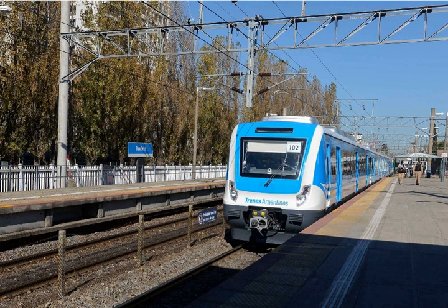The 2×25 kV autotransformer system is a split-phase electric power system which supplies 25 kV power to the trains but transmits power at 50 kV to reduce energy losses; it should not be confused with the 50 kV system. In this system, the current is mainly carried between the overhead line and a feeder transmission line instead of the rail. The overhead line and feeder are on opposite phases, so the voltage between them is 50 kV, but the voltage between the overhead line and the running rails remains at 25 kV. Periodic autotransformers divert the return current from the neutral rail, step it up, and send it along the feeder line. This system is used by Indian Railways, Russian Railways, UK High Speed 1 and Crossrail, French lines, most Spanish high-speed rail lines, Amtrak, and some of the Finnish and Hungarian lines.